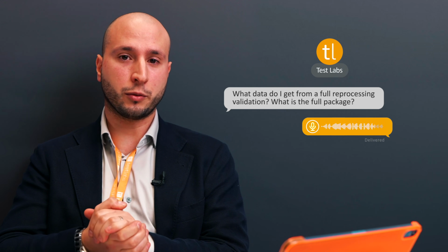A few more questions that you will need to answer is my device still biocompatible at the end of its service life? And do I have any residue, for example, accumulated over the course of its use within the healthcare systems? So when you perform a full validation, you will get all these answers from the various reports you get. So you get a full clean validation report, a disinfection report, sterilization, a reprocessing life cycle report, which will include, for example, some cytotoxicity, some biocompatibility testing at the end to prove that your device is still safe and hasn't changed any of these adverse effects, for example, or the materials haven't decomposed or anything like that. So that would be, for me, the full package for reprocessing validation.